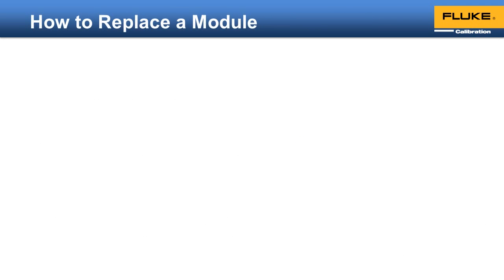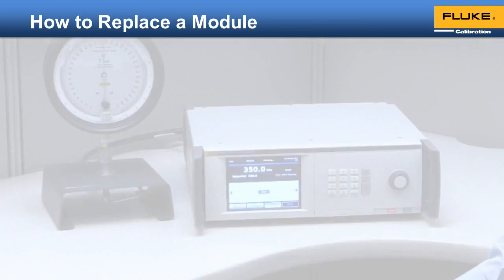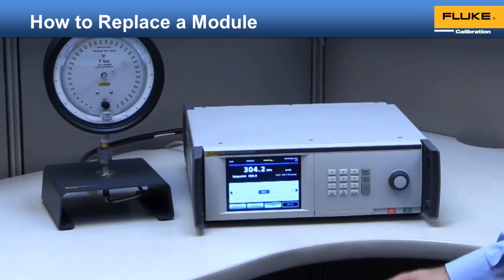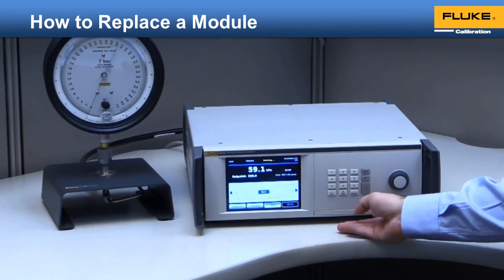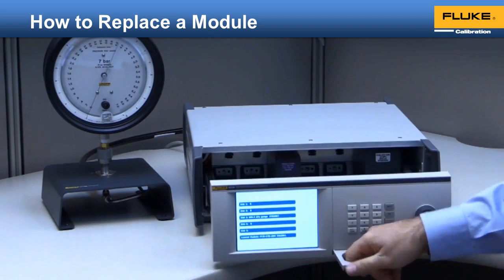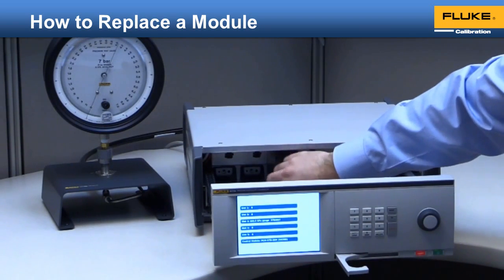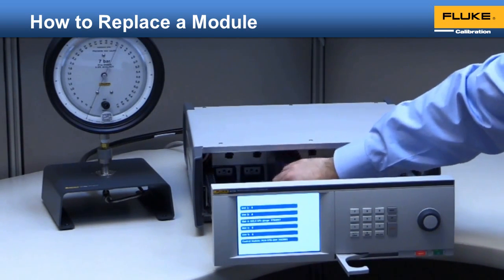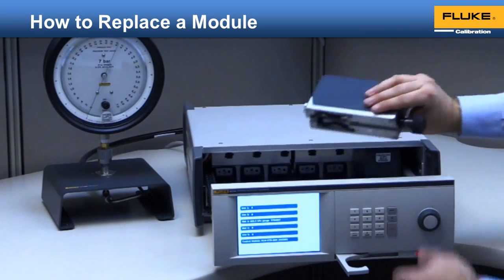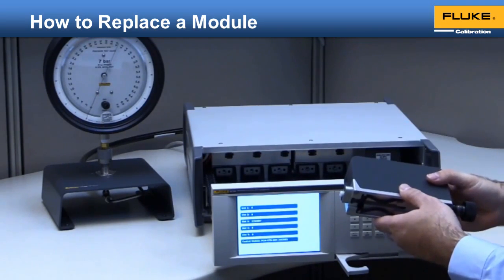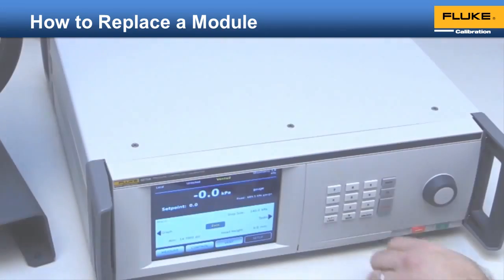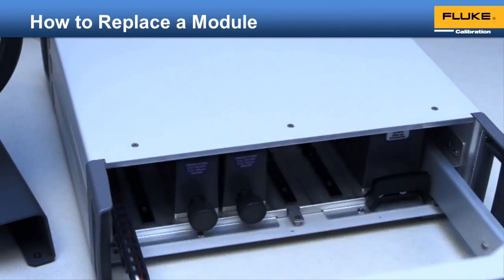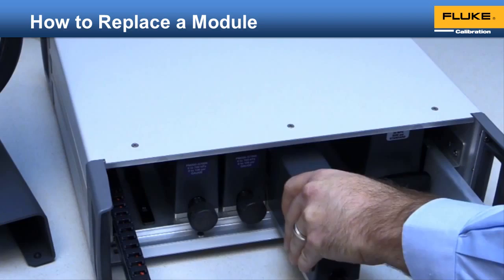Just how easy is it to change out or add an additional measurement module? First, open the front panel by pulling the door latch out. The front panel opens like a drawer. When the door is opened, the system automatically vents the test pressure. Simply unscrew the module that needs to be removed. To install a new module, slide it in. The slot rail will ensure that it's properly aligned.